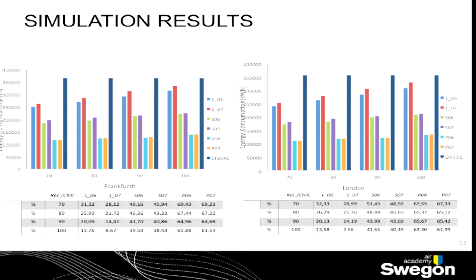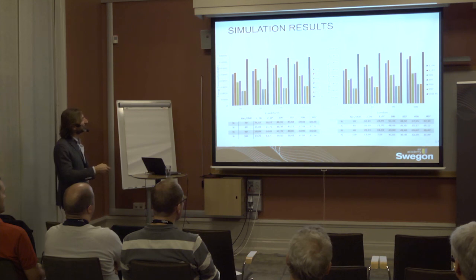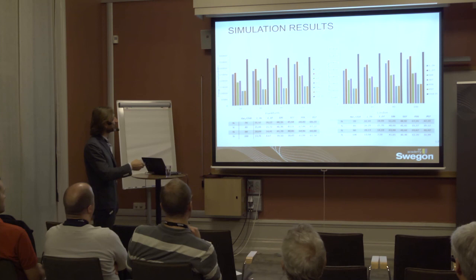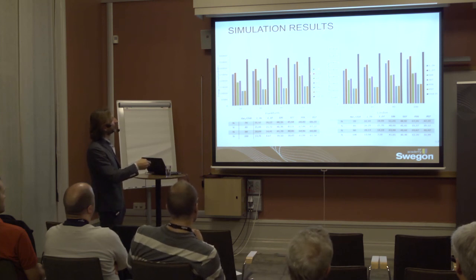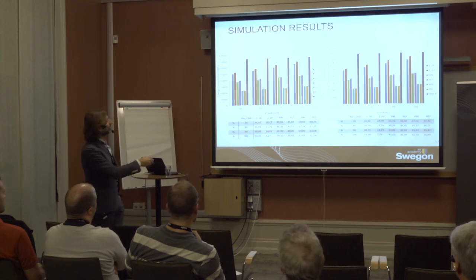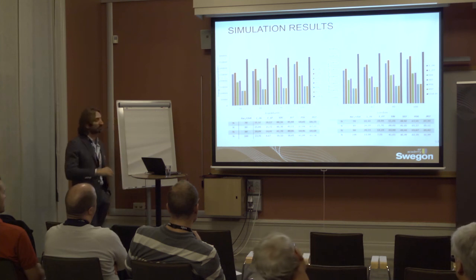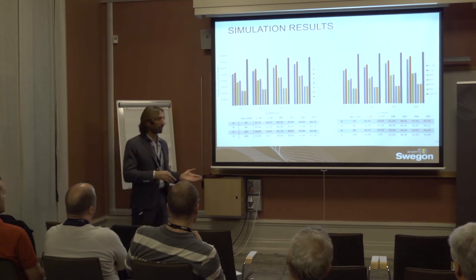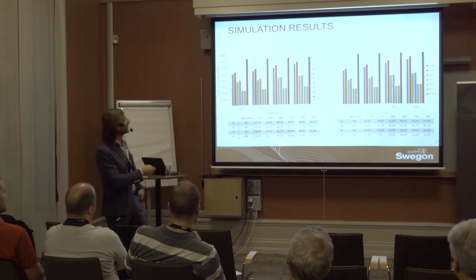And with 2 different filtering efficiencies. So this is an F7 filter and this is an F6 filter on both sides, because we want to have a complete overview. These are the results in terms of energy spent by the systems. So this is the energy spent by the chiller free cooling. That's always the same, of course, because it is only for comparison. And this is the energy spent to run a system with a single plate heat exchanger. So this red one with F6 filters. These are for a series of 2 plate heat exchangers, and this is with a parallel of 2 plate heat exchangers. This is due to the cutting in pressure losses due to the parallel on the outside air linked to this system.